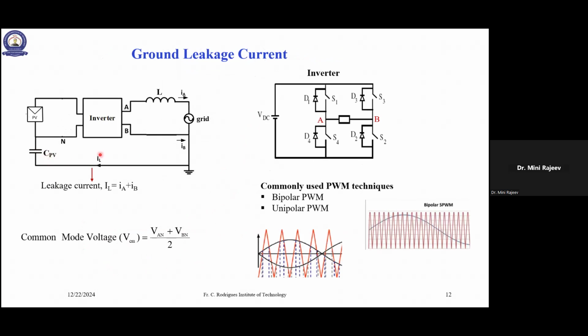I also said that the PV panel metallic frame is grounded for safety reasons, and the single phase grid neutral is also earthed for safety reasons. As per standards, that is a requirement. So there is a closed path like this for the current to flow.